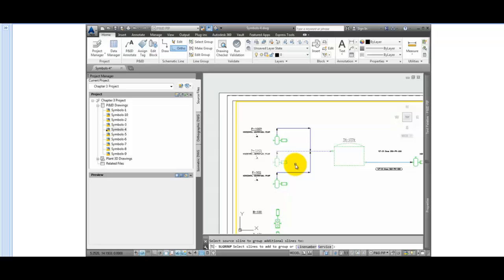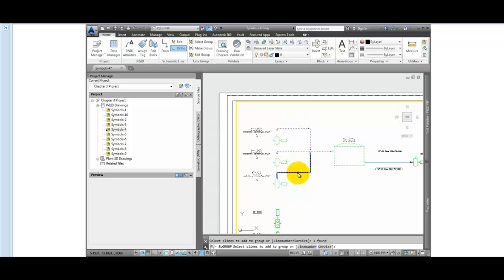Once the line is selected, you'll be prompted to select additional lines to add to the group. Select the pipelines from pumps P100 and P102. Once these items are selected, instead of pressing Enter to complete the command, press L first and then press Enter.